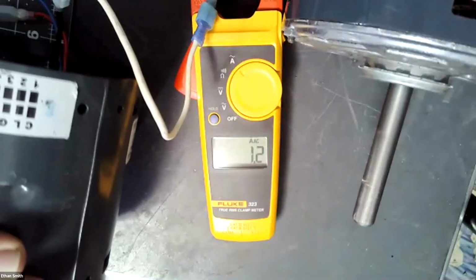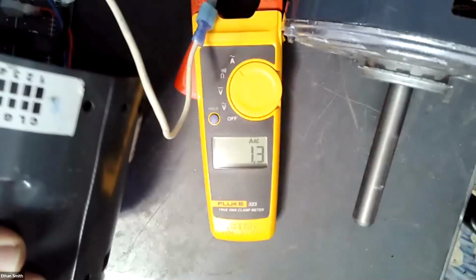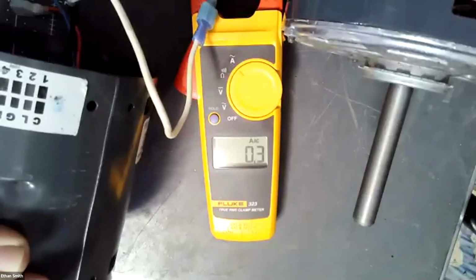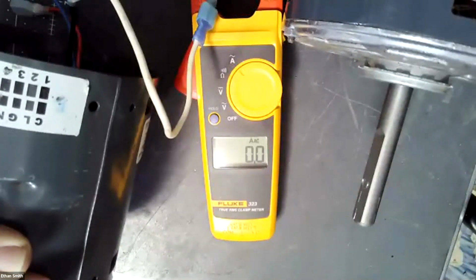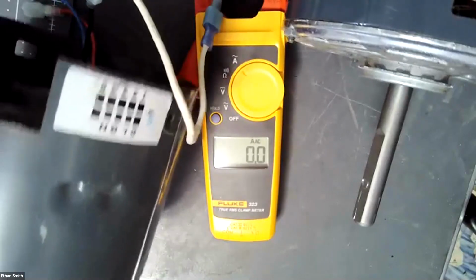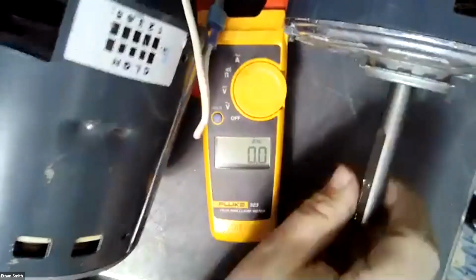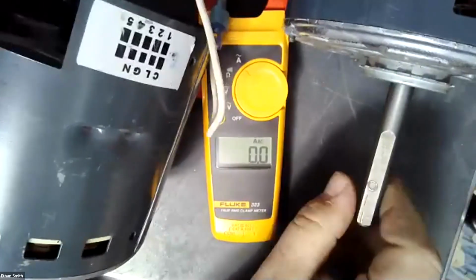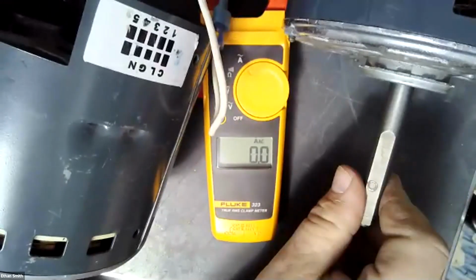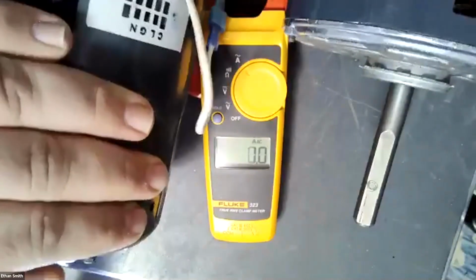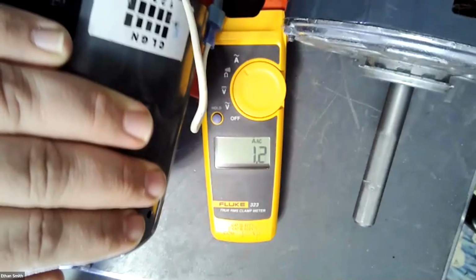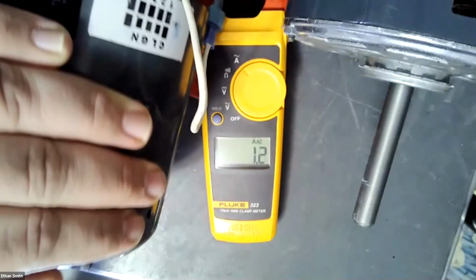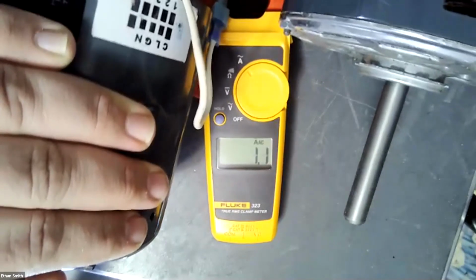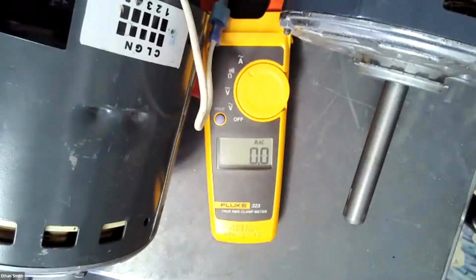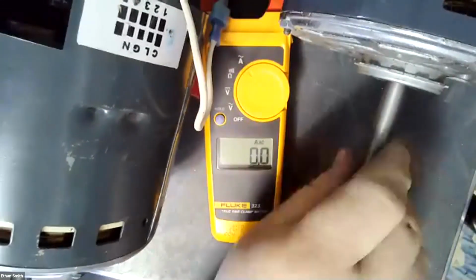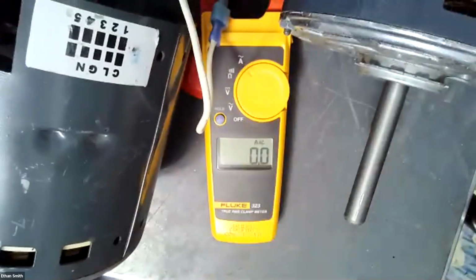Look at that. Okay, we got it to spin. So it's important that even though we're able to generate power here, if we want to do useful work with it, we've got to match our frequency and our voltage. We're running really high voltage, really high frequency, and you notice this thing soft starts. That's because we're running that frequency so high through those windings that it has a tough time grabbing hold of that rotor and getting it moving. It's just not designed to run at that high frequency.